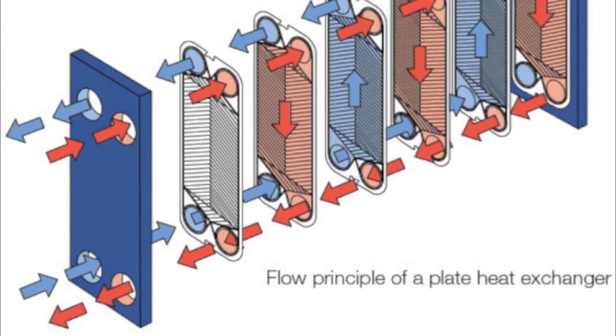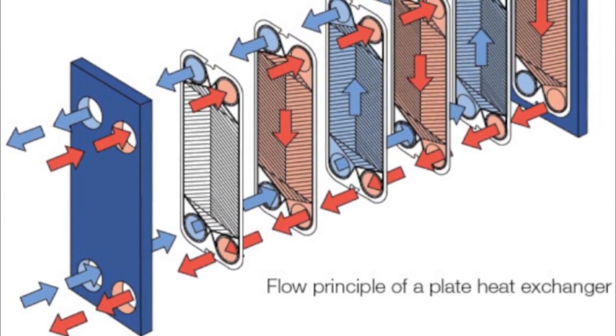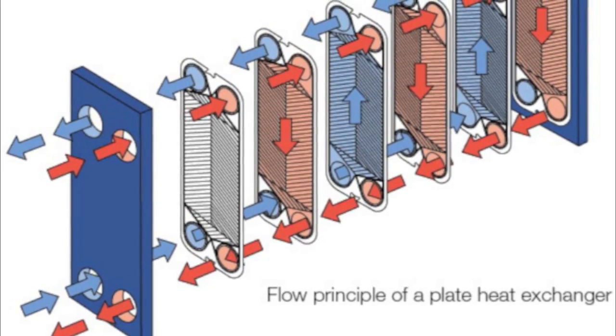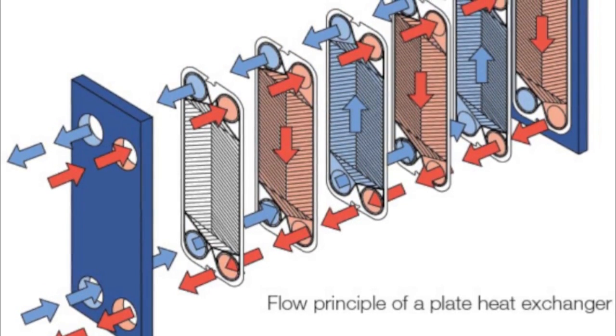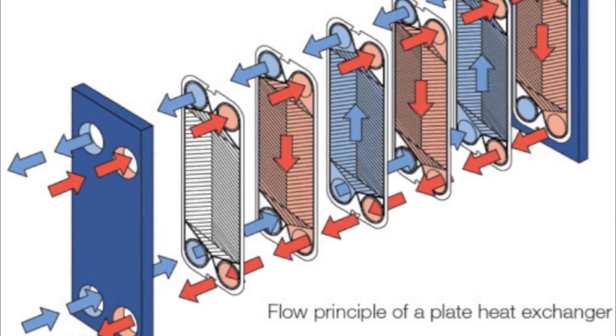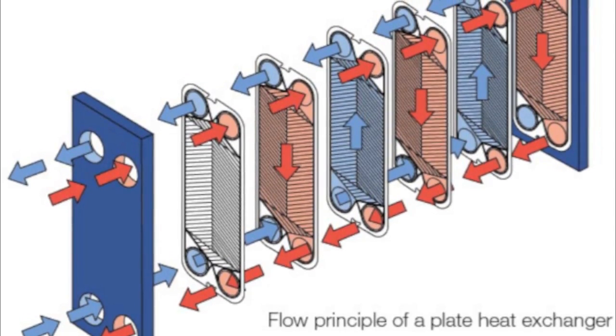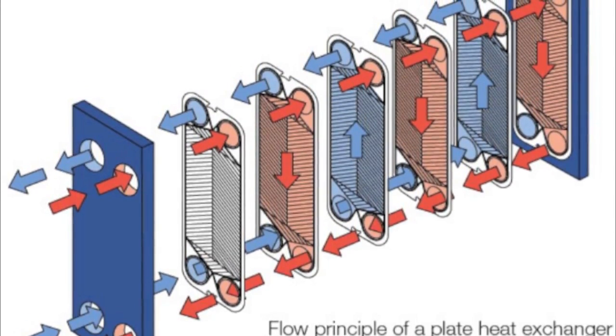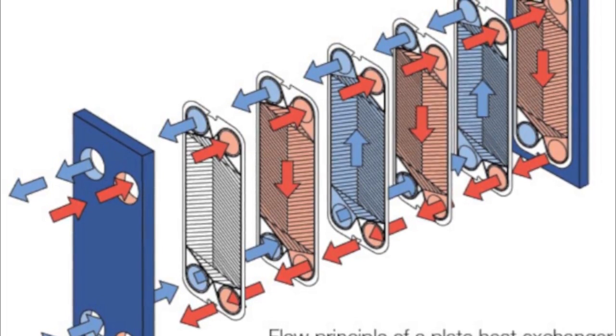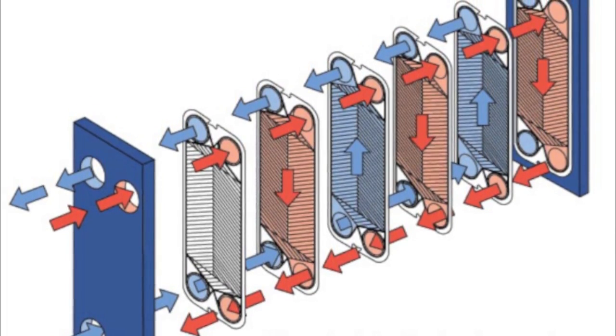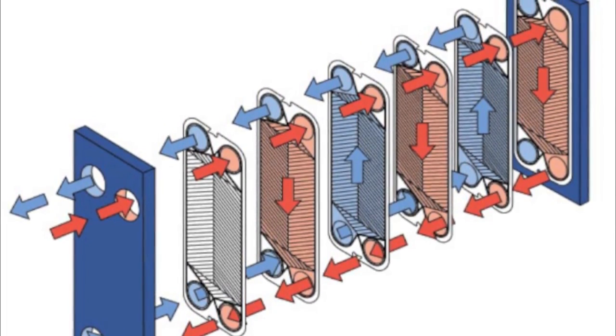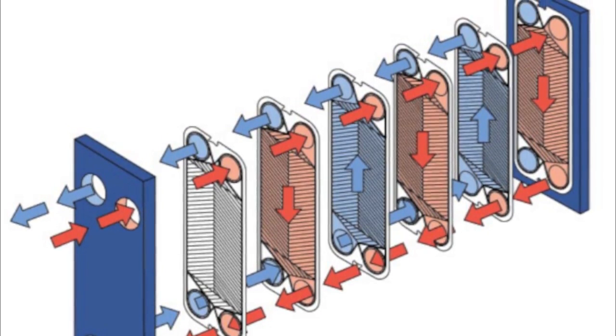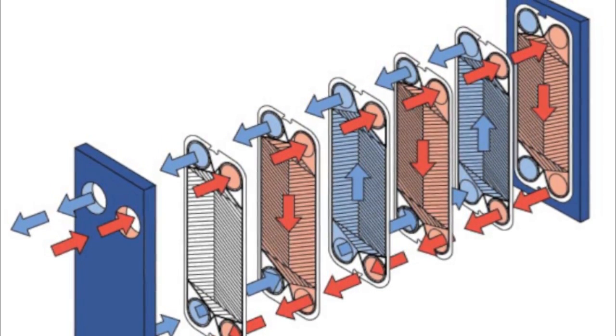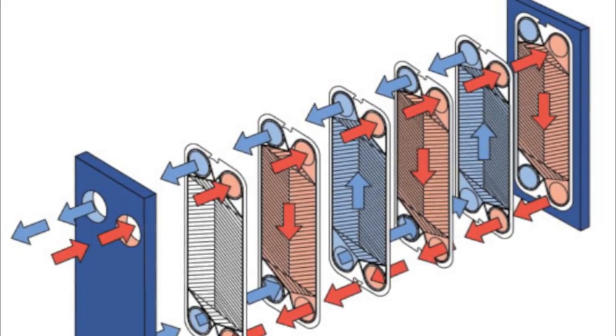Let's take a look inside the heat exchanger. Plate-type heat exchangers operate using counterflow, meaning the hot and cold fluids flow in opposite directions. As shown in the diagram, the plates are arranged in such a way that the flow bounded by each successive plate alternates between hot fluid and cold fluid. In a heat exchanger, the factors that affect heat transfer include temperature difference between the fluids, thermal conductivity of the barrier between the fluids, and the surface area for heat transfer.